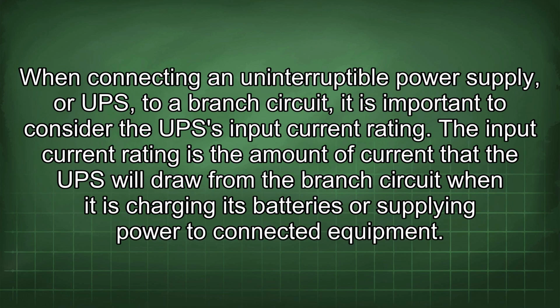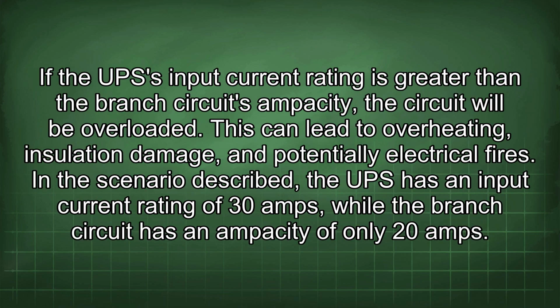When connecting an uninterruptible power supply, or UPS, to a branch circuit, it is important to consider the UPS input current rating. The input current rating is the amount of current that the UPS will draw from the branch circuit when it is charging its batteries or supplying power to connected equipment. If the UPS input current rating is greater than the branch circuit's ampacity, the circuit will be overloaded. This can lead to overheating, insulation damage, and potentially electrical fires.